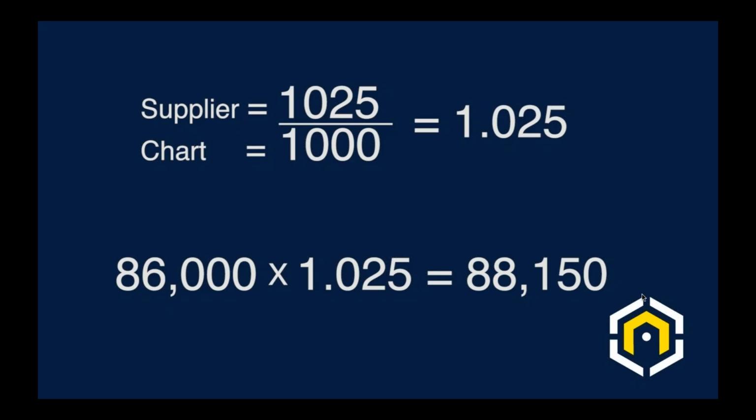Hey, Joe. Yes, sir. I got one question that came in. How do you clock the meter with liquid propane? With liquid propane, what you would do is you buy what's called a sub-meter. You can buy gas meters for apartments, and you would just install the meter in line temporarily in the basement while you're doing your input tests.